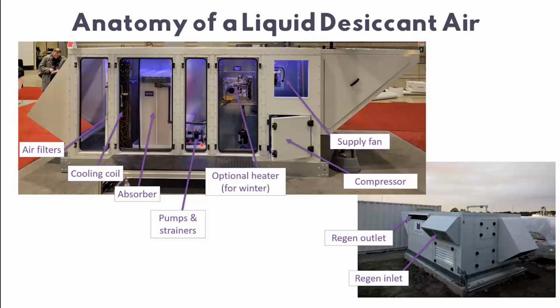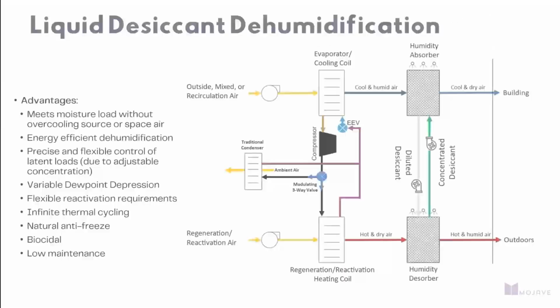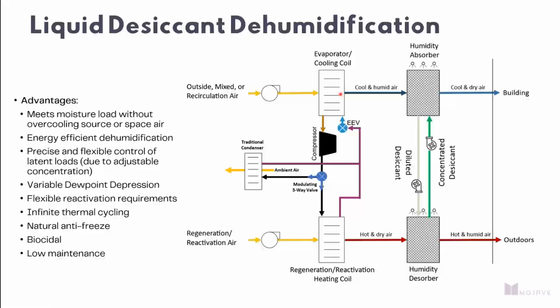Now on the regeneration side, just to give a visual of that, quite literally an outside air tunnel, you pull air in, there's a coil behind here and a fan. You heat that air up, pass it through another media like the one I've shown, evaporate the moisture that you've collected in that desiccant out, and dump that moisture back to the ambient environment. So going back to this slide for 1 second, very conceptually, we're moving thermal energy or BTUs from one stream to the other via refrigerant, and then we're moving moisture from one stream to the other with liquid desiccant being that medium.